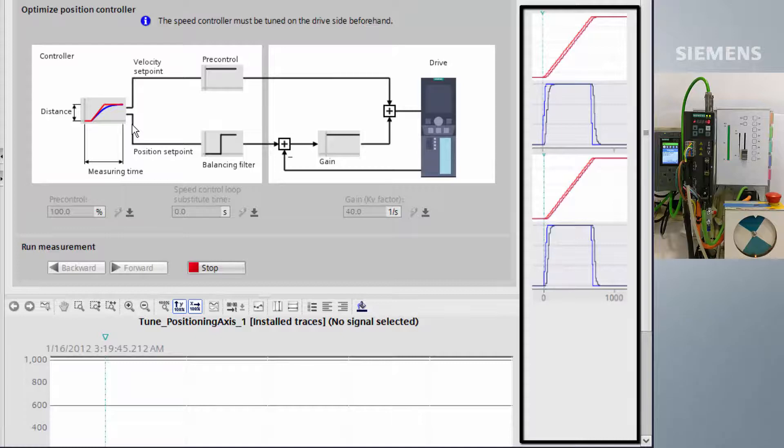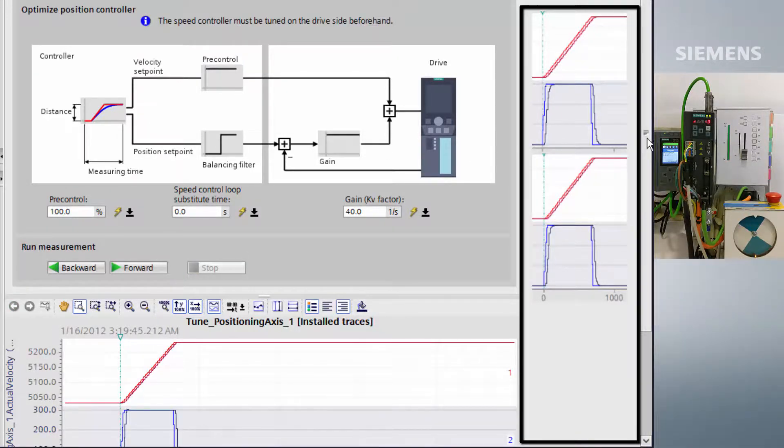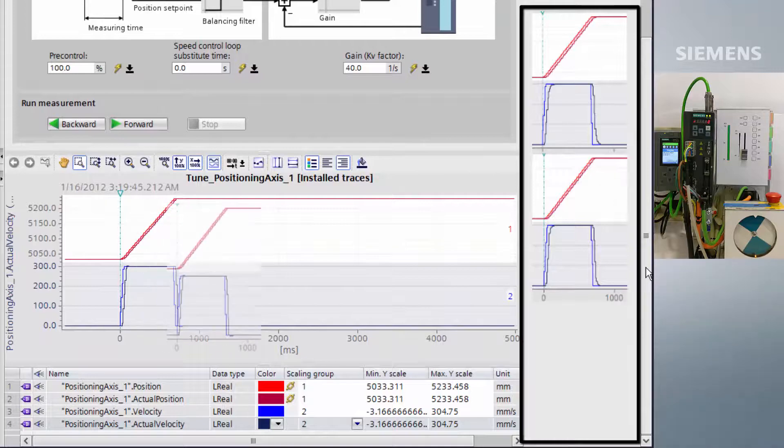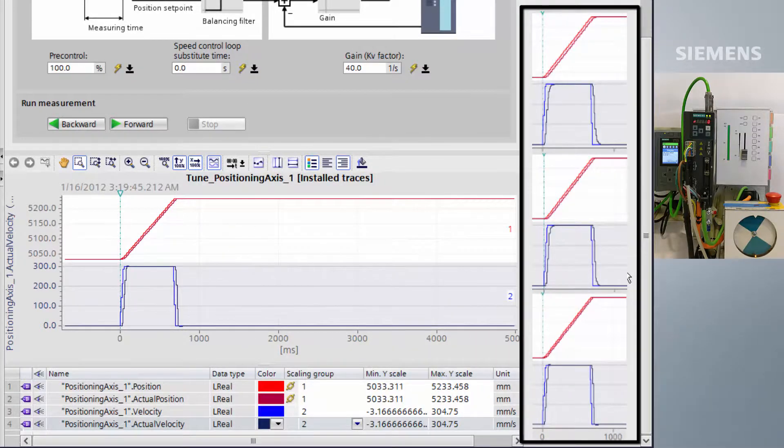At 100% pre-control, we have just started to overshoot. This is usually an indication that the drive is at its limit of tuning.